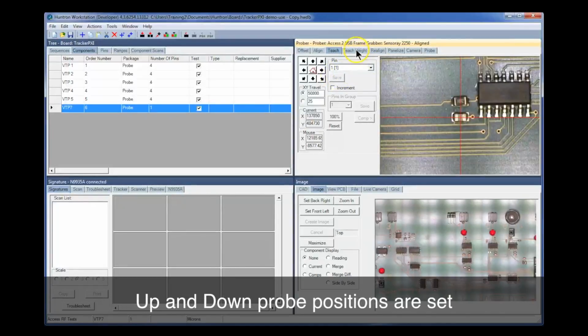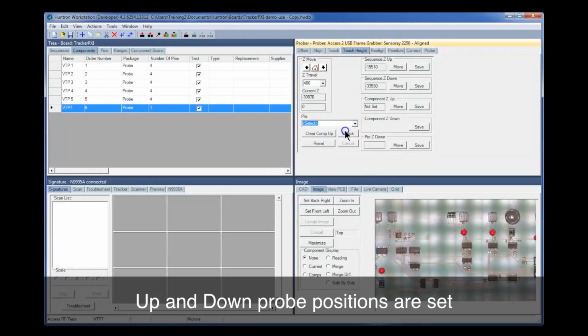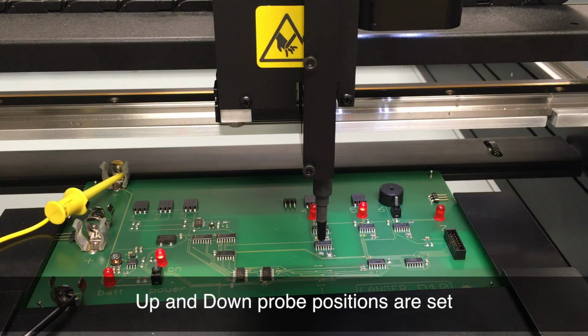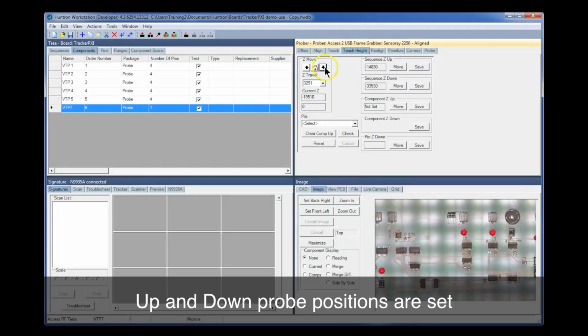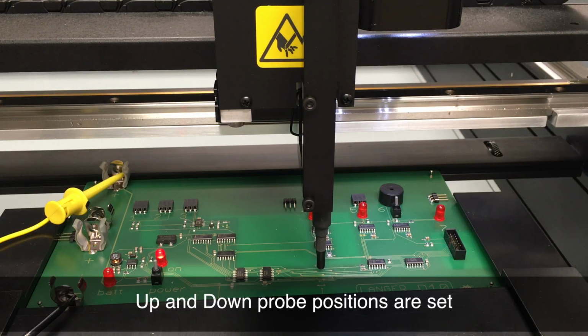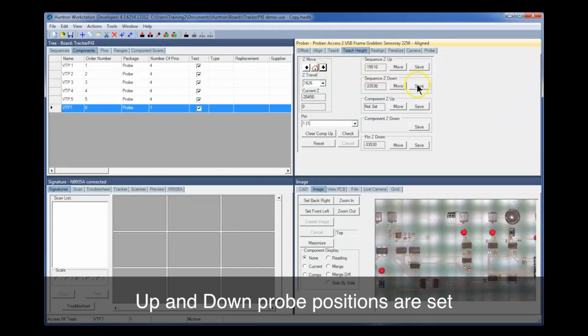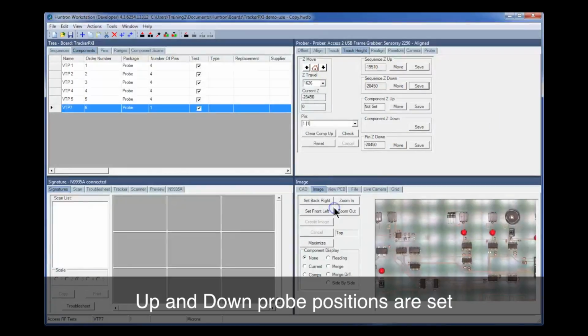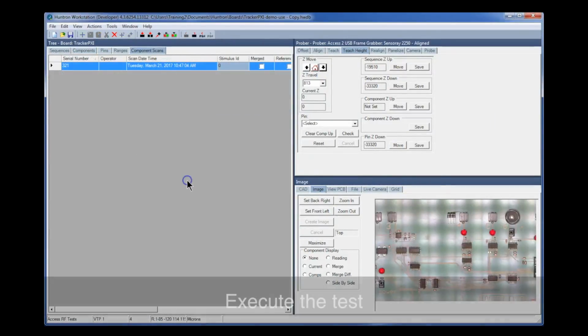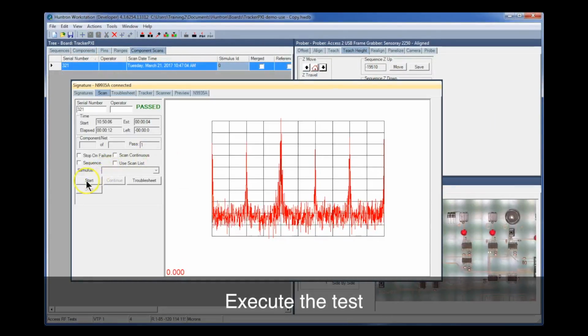The last step is to teach the vertical positions for the probe. The up position designates the position as the probe moves between points, and the down position sets the vertical position of the probe when a measurement is taken. The probe does not make contact with the CCA, but is positioned very close to capture the strongest possible signal. The up and down positions can be set individually or globally for the entire sequence. The test is now ready to execute.